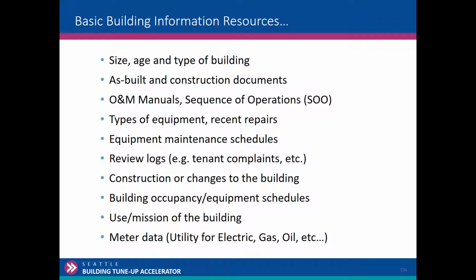So size, age, type of building, O&M manual, sequences of operation, types of equipment, recent repairs, maintenance schedules, construction or changes to the building that will affect, if there's construction going on, tenant improvements, what's going on there, building equipment schedules, use of the building, and then meter data. And you'll have most of this from just the benchmarking data that you'll have, and I'll talk about that in a minute. But that's the kind of information that you're going to need. If you're a service contractor, you may have a lot of that information for this building already.